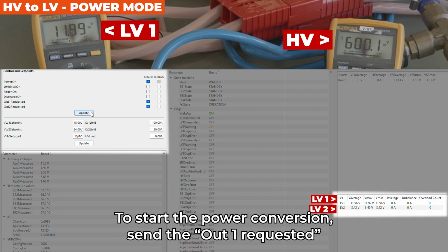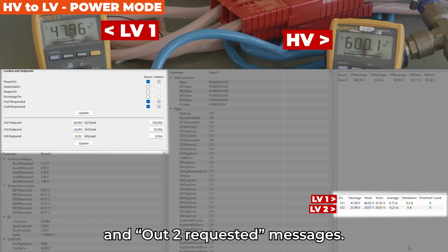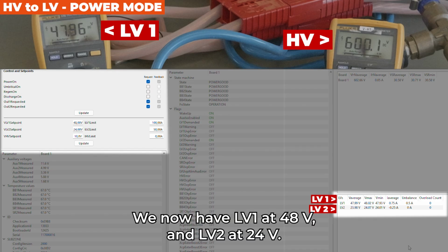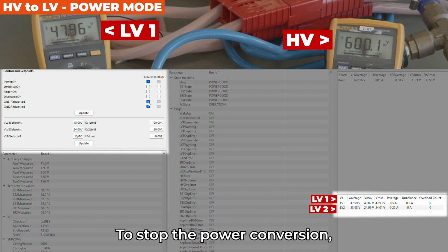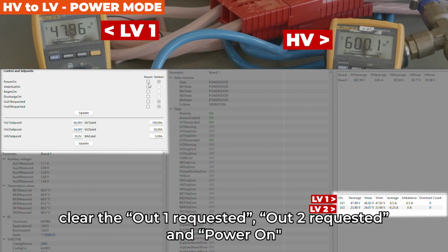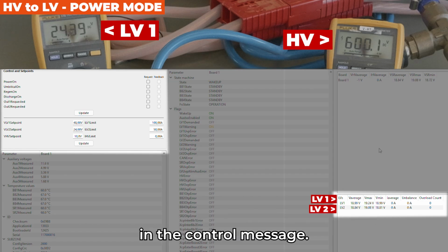To start the power conversion, send the out1 requested and out2 requested messages. The power conversion starts. We now have LV1 at 48 volts and LV2 at 24 volts. To stop the power conversion, clear the out1 requested, out2 requested, and power on in the control message.